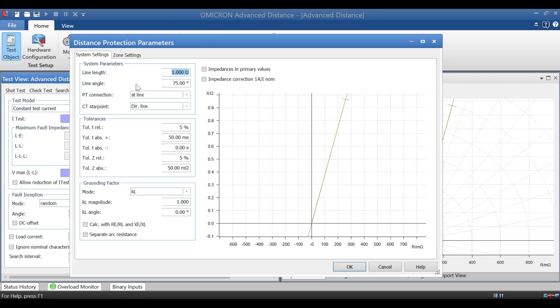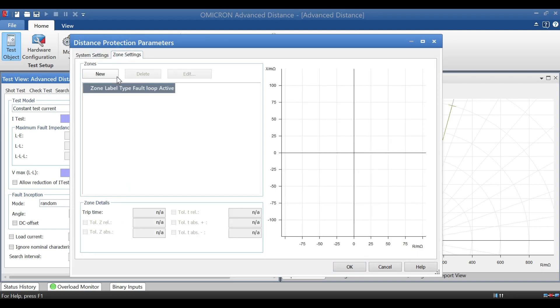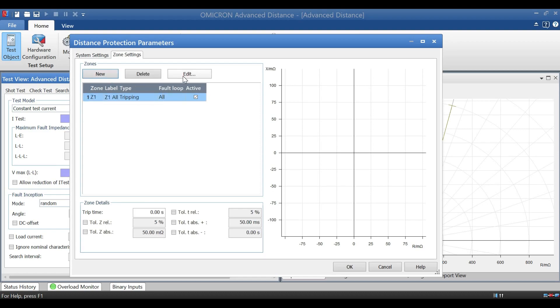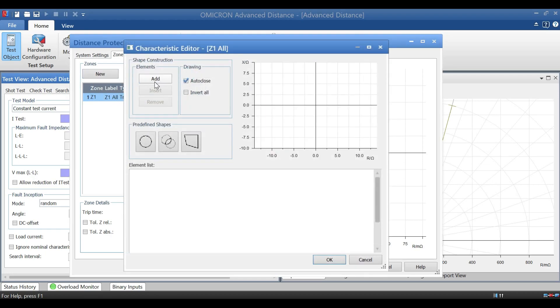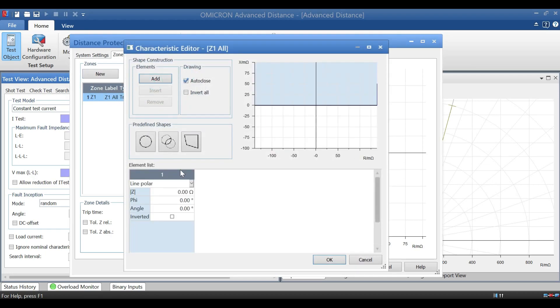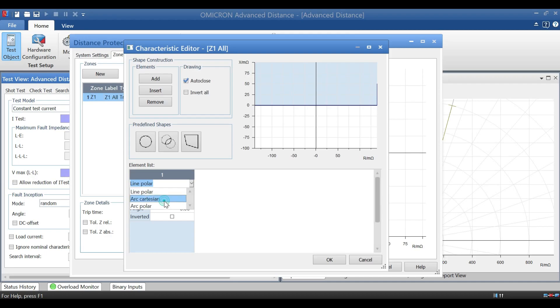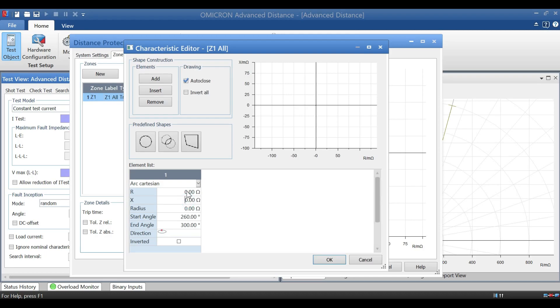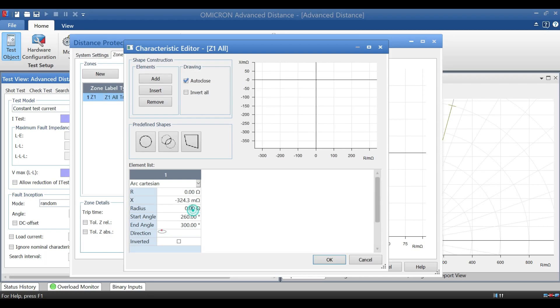So we can go for zone setting. Over here we have to create new zone and go for editing. Over editing, click add. On addition of this block, you can able to see the element list. In this, you have to select arc Cartesian. And when you select, we will get a default value over there. First R value, no need to fill, just leave empty as 0. Next go for X value. X value for Z1 is minus 0.3243, and R value for Z1 is 0.2935. And select OK.